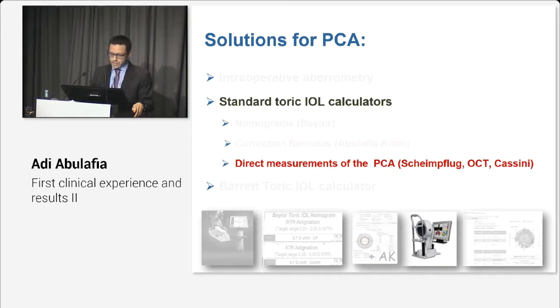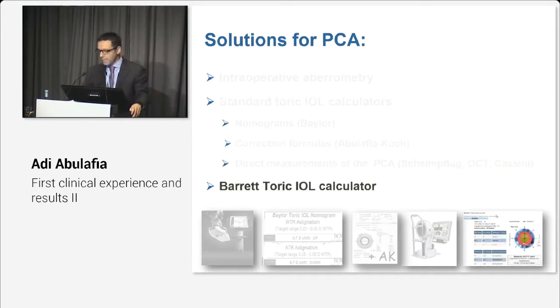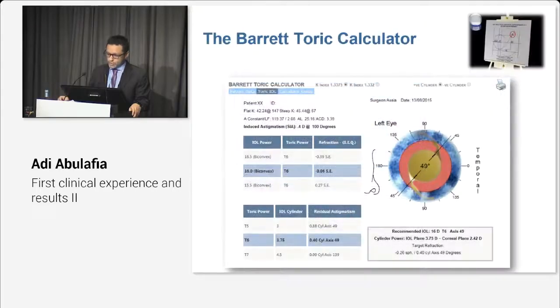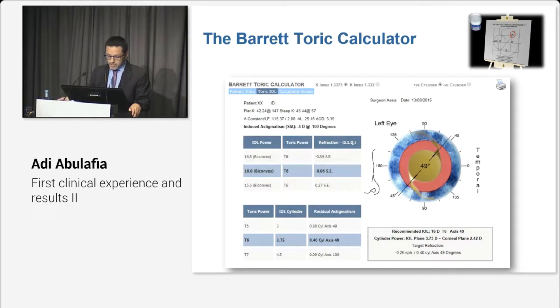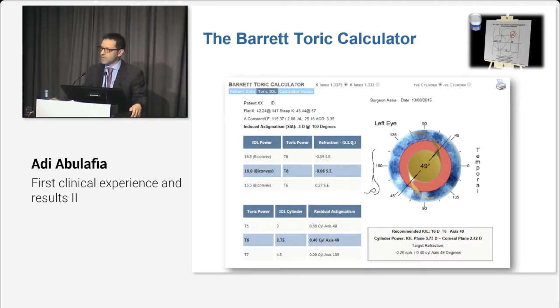A third option is to use the Barrett Toric calculator. The full version is available online as well as on the LENSTAR device — it's an all-in-one solution. It is based on the Universal II formula and has an integral solution which takes into account both the effective lens position and a mathematical model that calculates the estimated net corneal astigmatism utilizing anterior corneal-based measurements.